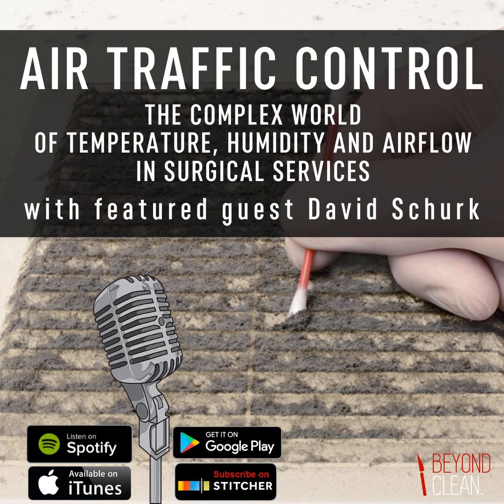What's going wrong there? Sure. Well, I don't want to speculate specifically with what's going on in either of those locations, both Seattle and Dallas. But I will say that I have seen many hospital facilities where the HVAC systems are basically breeding grounds for biological growth, mold, mildew, fungus, things of that nature. And what I have seen is the occurrence of those issues, particularly inside air conditioning units, in the cooling coil cabinet areas, where you've got moisture from condensate and a dark, cold environment.